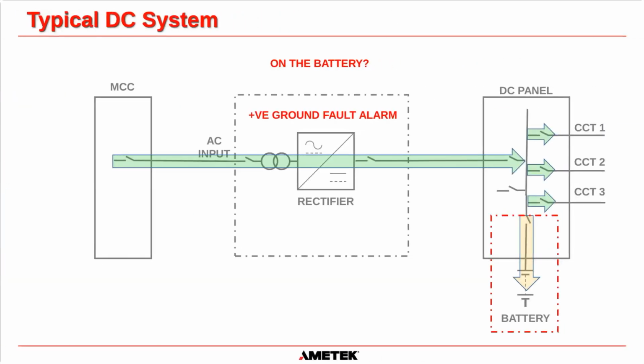So let's continue. Let's go down to the next culprit that a lot of people point towards. They think that the fault is on the battery. Very rare that you're ever going to see a ground fault on a battery, but it can happen. You can have electrolyte leaking from a very poorly maintained battery, and that electrolyte can track all the way down from the positive post down to the battery rack and find some metal through the plastic in that battery rack and cause a soft fault on the battery. It is possible, very rare though.